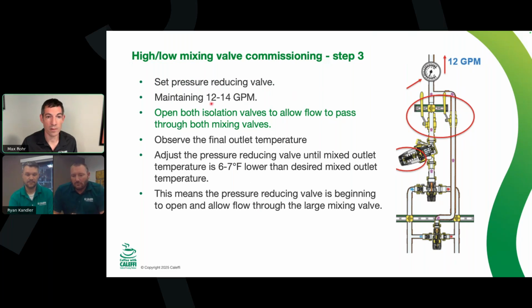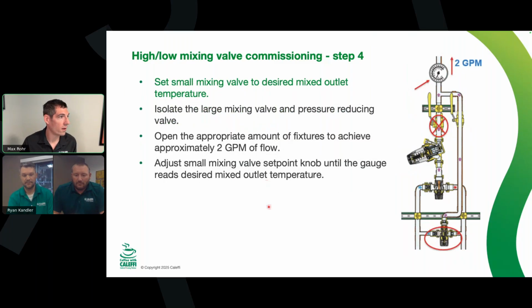If you had a bunch of people in a hotel opening fixtures as you're trying to do this, you are really chasing your tail a little bit to know whether we're steady at 12 or steady at 2. That's what we meant with the pole. So what's the last step here? Yeah, at the last step, you go back and slow that flow down to that 2 GPM, and then adjust that smaller mixing valve to the desired outgoing temperature of 120.